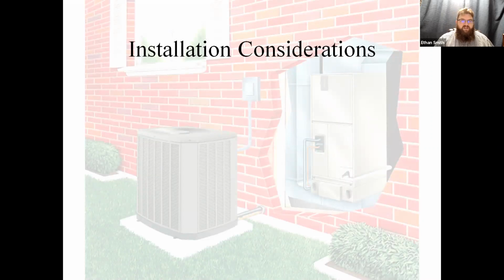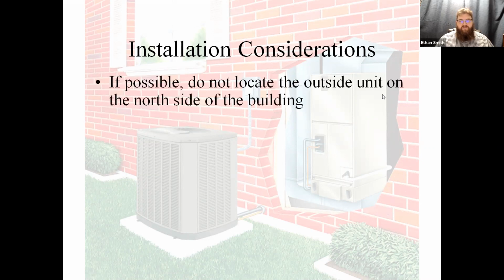Okay, other things to consider when you guys are installing or servicing heat pumps. Some of you may have noticed that my heat pump in the background on all these pictures is sitting on a slab. That's kind of a no-no, so we'll talk about that. But if possible, we don't want to locate the outdoor unit on the north side of a building. These things are made to extract heat from the outdoor conditions. And if they're on the north side of the building, that's usually the coldest side of the building.